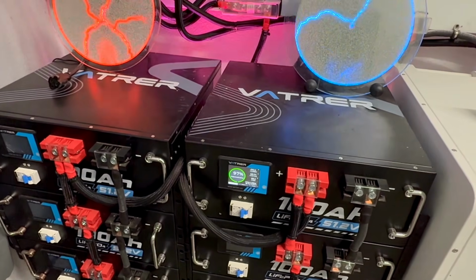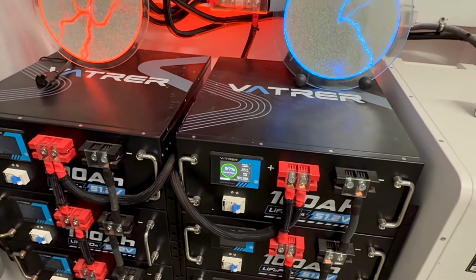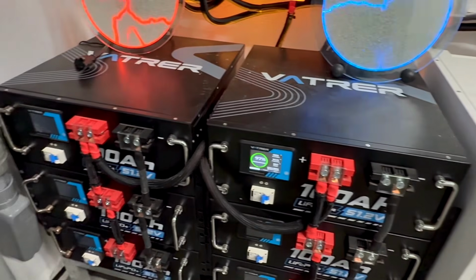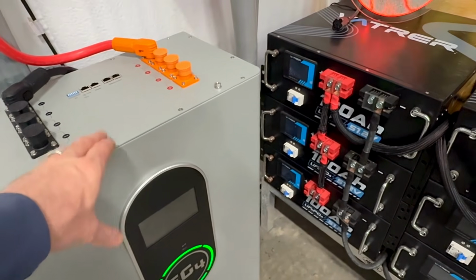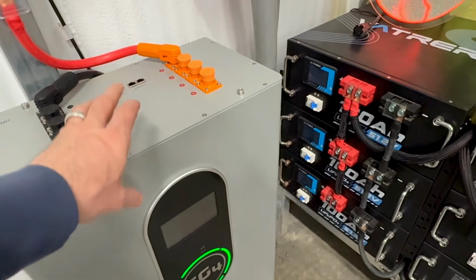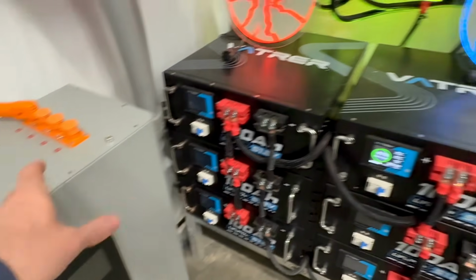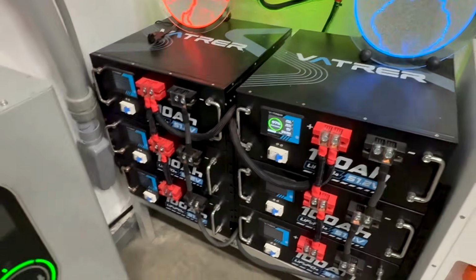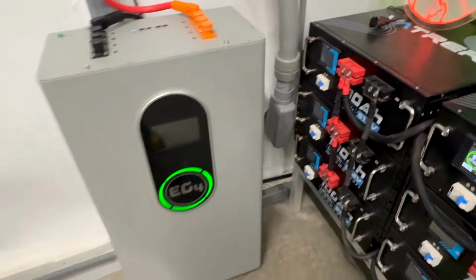You can look at your cell voltage and see where you're at, and get a good idea how close to 100% it really is. Most BMSs will kick off once your cell reaches 3.65 volts for a single cell, but definitely charge them all up to 100%, your existing bank and the new battery as well. Then when you connect it all up, it should be in good shape.